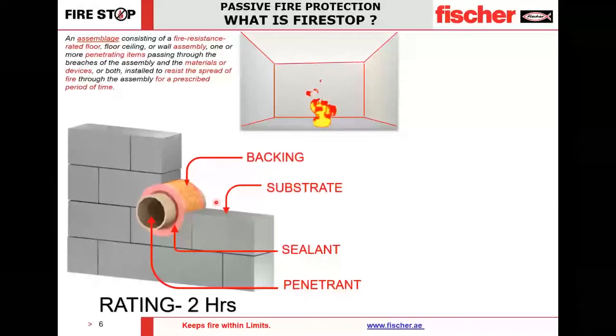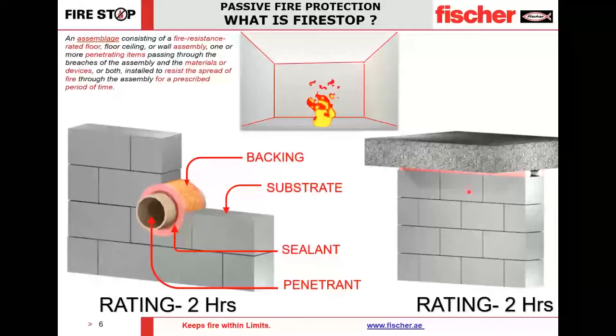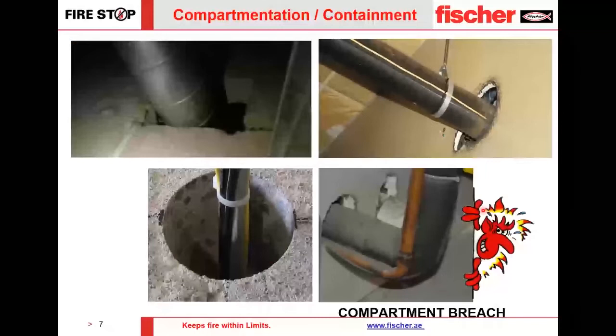Similarly, the civil joint between a fire-rated wall and the floor is inherently constructed with a breach. A fischer Firestop system is applied to achieve the required rating and close that breach. Civil joints are also a system consisting of the substrate, backing material, and the fischer Firestop sealant. Examples of these breaches are seen frequently on building projects. Flames, smoke, and toxic gases can escape through breaches as small as a pencil hole — though often they are much, much bigger.